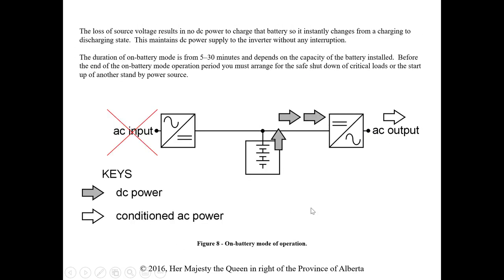If we lose AC, the system instantly changes from charging to discharging state — the DC battery becomes the actual supply to the inverter, and we still get AC output to the load. The duration of on-battery mode is 5 to 30 minutes, depending on battery bank capacity. Before the end of that period, you must arrange for a safe shutdown of critical loads or startup of another standby power source such as a backup generator.